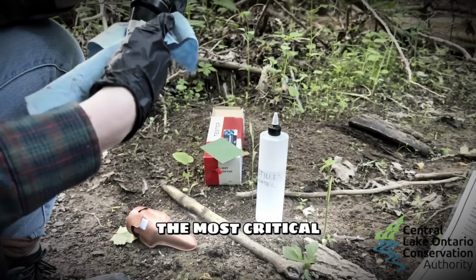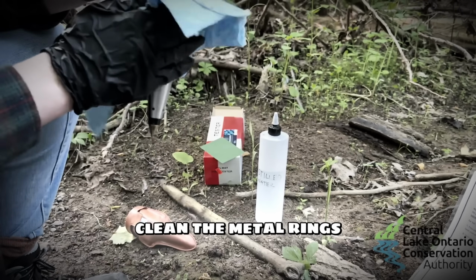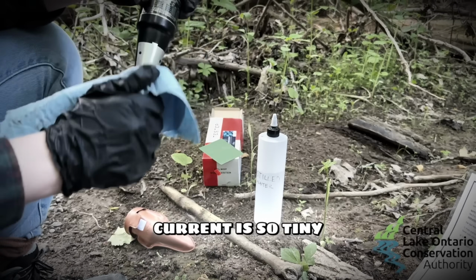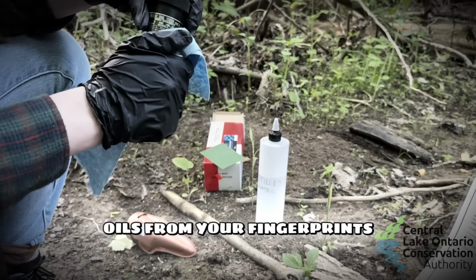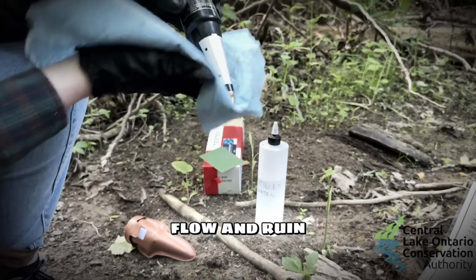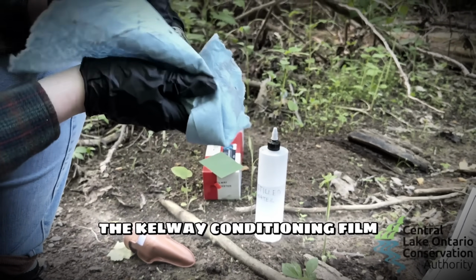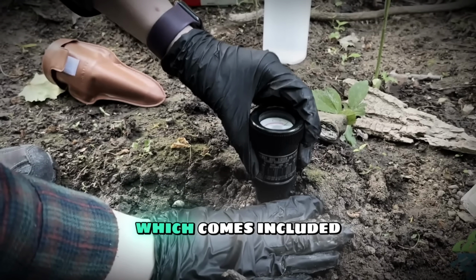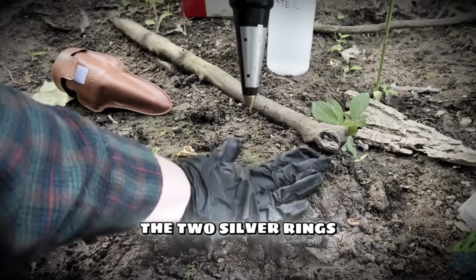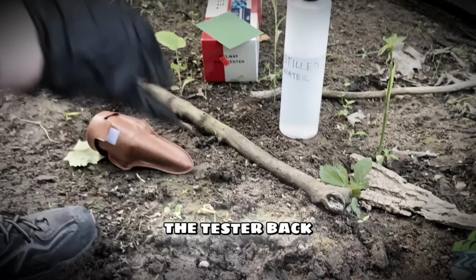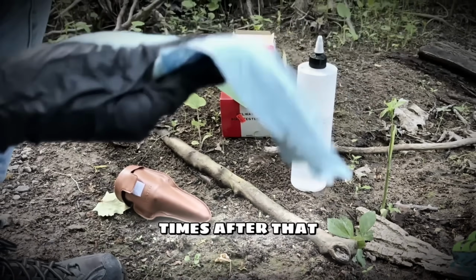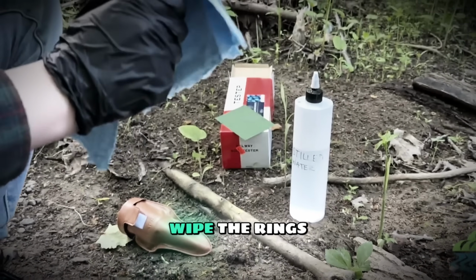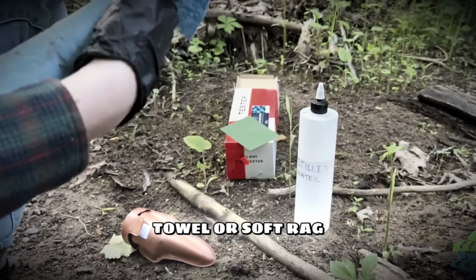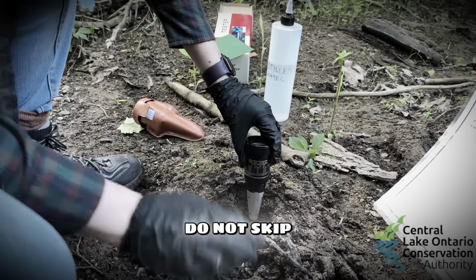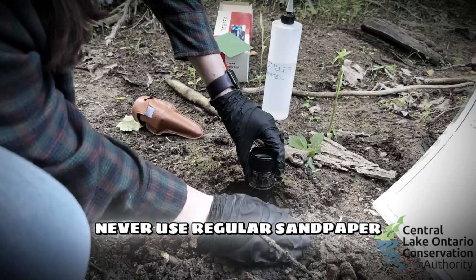Step 1 is the most critical. Clean the metal rings. Because the electrical current is so tiny, even the natural oils from your fingerprints can disrupt the flow and ruin the reading. You will take the Kelway conditioning film, which comes included with the meter, wrap it around the two silver rings, and gently rotate the tester back and forth 2 or 3 times. After that, wipe the rings completely clean with a paper towel or soft rag. Do not skip this step and never use regular sandpaper.